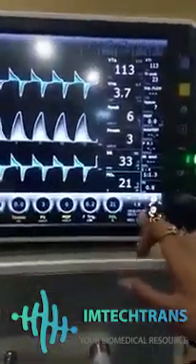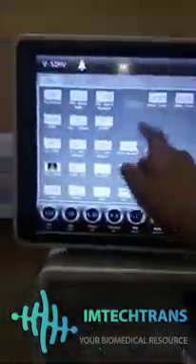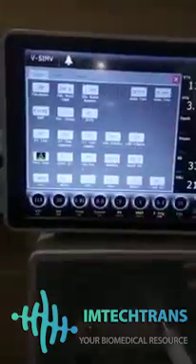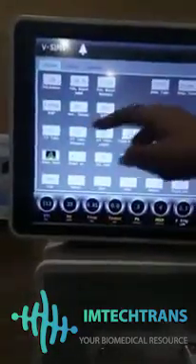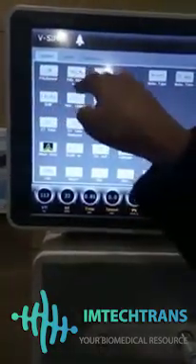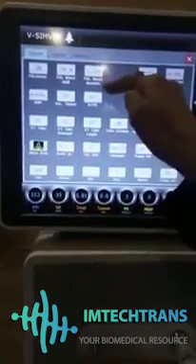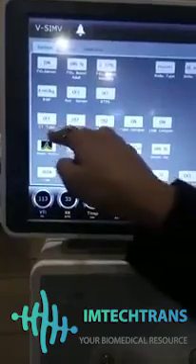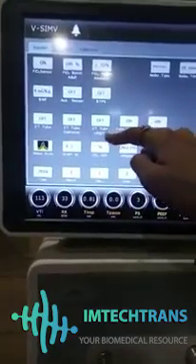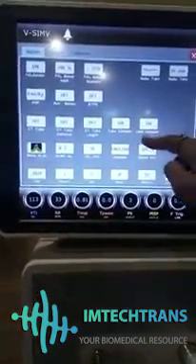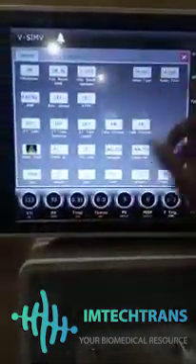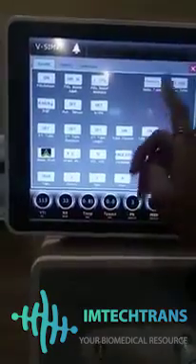Let's talk about the setting. So go to the setting. Now you can select all the parameters from this setting, like FiO2 sensor, FiO2 boost for adult, FiO2 boost for neonatal, patient body weight also, sensors, BTPS, ET tube diameter, ET tube length, ET tube compensation and leak compensation, and so on. So all the parameters you can select from here, and you can switch on or off also.